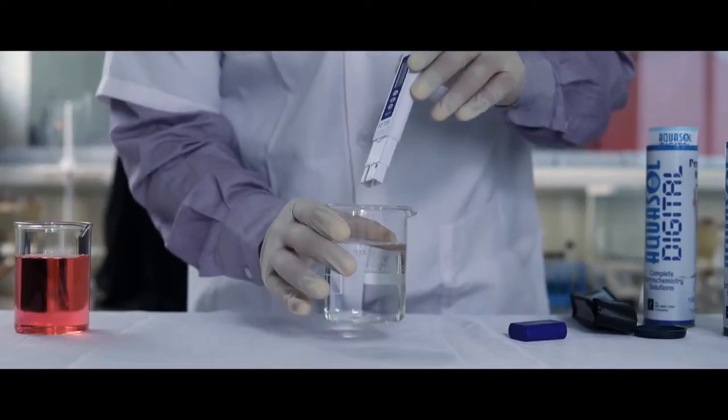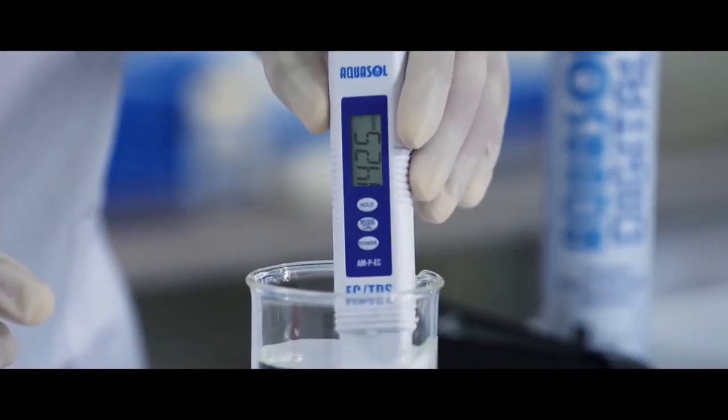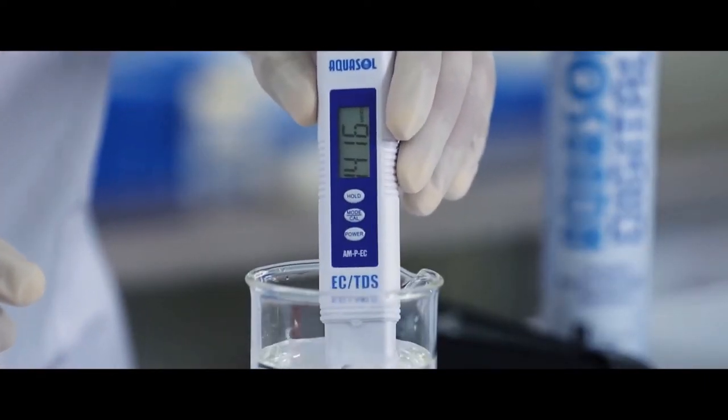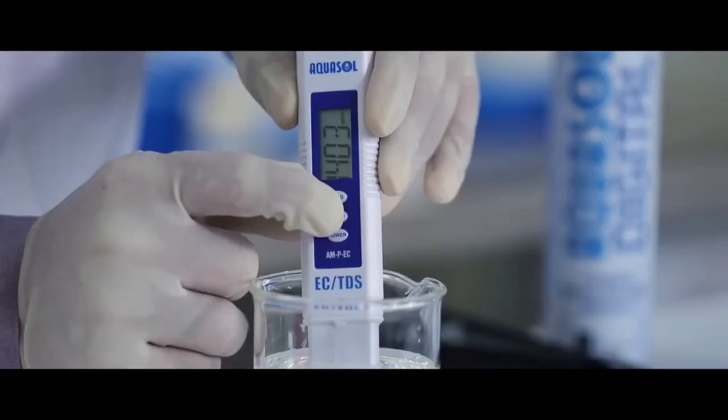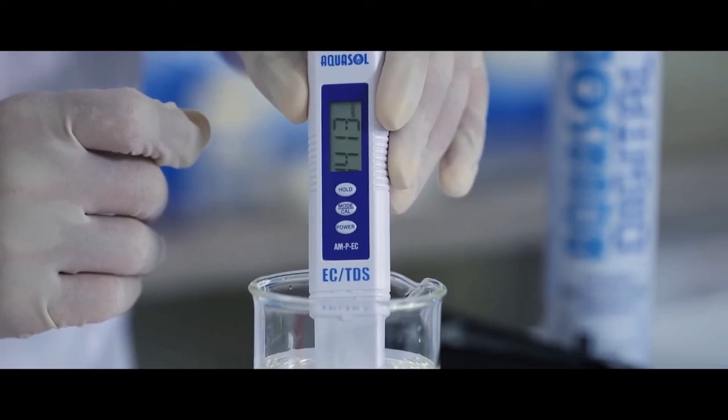Calibration: dip the electrode in the 1413 buffer solution. Stir gently till the reading is stable. Press and hold the cal key. The display will read 1413.